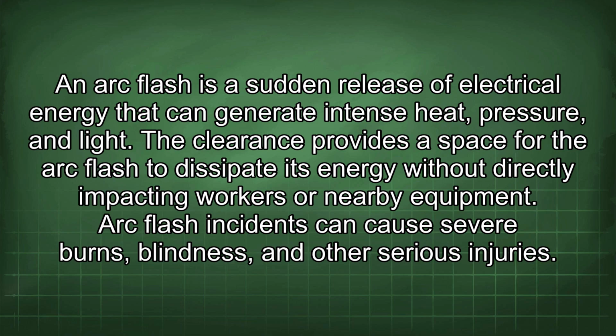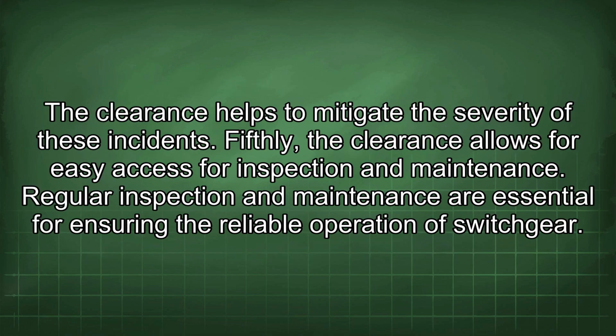The clearance provides a space for the arc flash to dissipate its energy without directly impacting workers or nearby equipment. Arc flash incidents can cause severe burns, blindness, and other serious injuries. The clearance helps to mitigate the severity of these incidents. Fifthly, the clearance allows for easy access for inspection and maintenance.